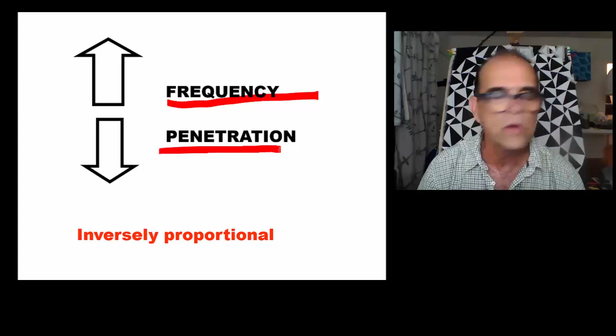Frequency and penetration are inversely proportional, and this is the most important here. The more the frequency of the transducer, the less the penetration of the transducer. This is why transducers with high frequency that have good quality are not good for deeper organs like the kidney, like the aorta. High frequency transducers are good because they have good quality pictures and are good for superficial organs like the thyroid, like the breast and the testicles.